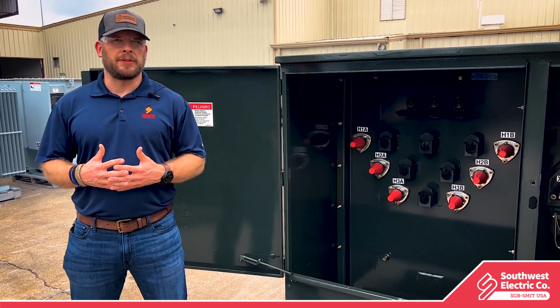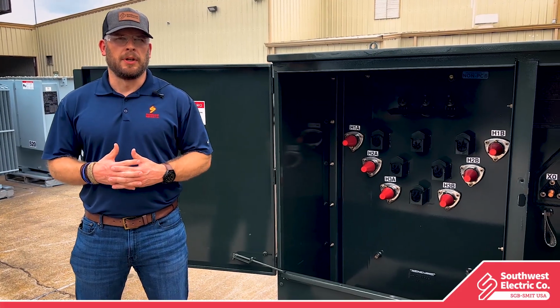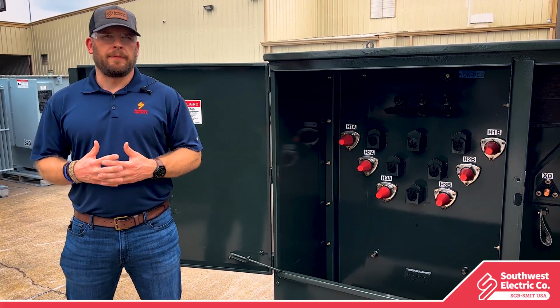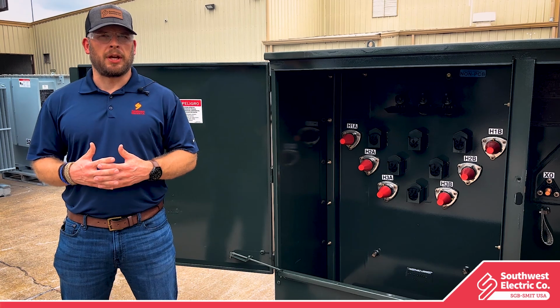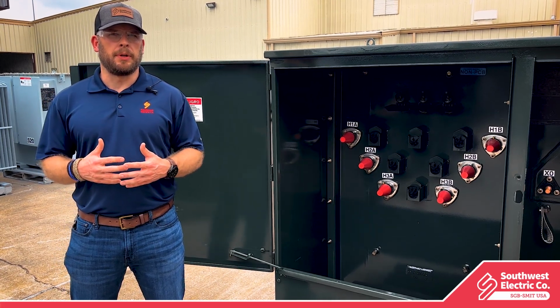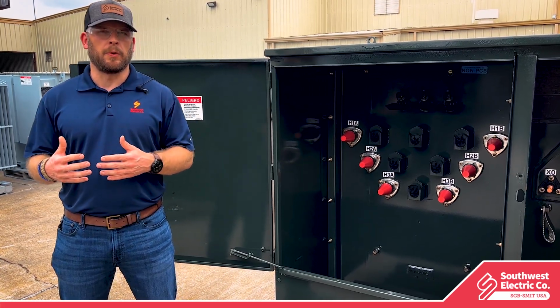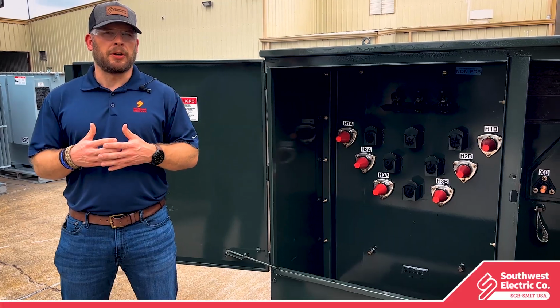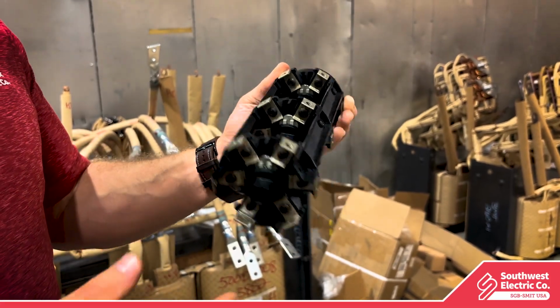A tap changer is a mechanism built into transformers that allows for the regulation of output voltage. We use them for when incoming voltage fluctuates or when the load changes. Being able to alter the input allows you to maintain a stable voltage level for your equipment, making it a critical component for safety and efficient operation.